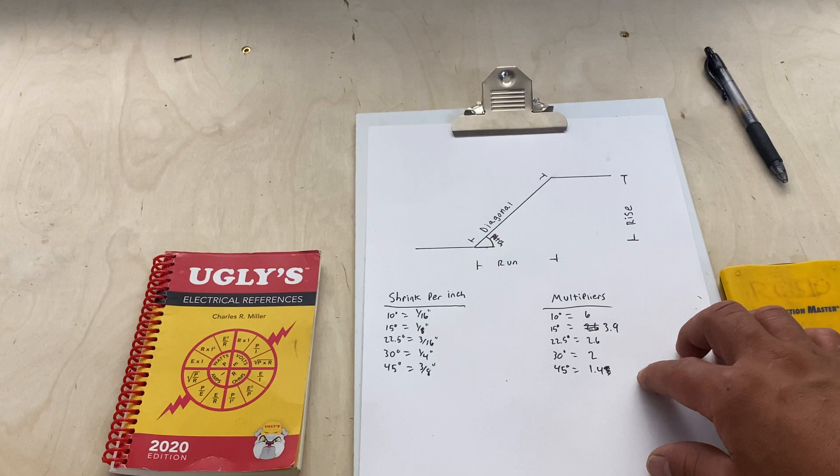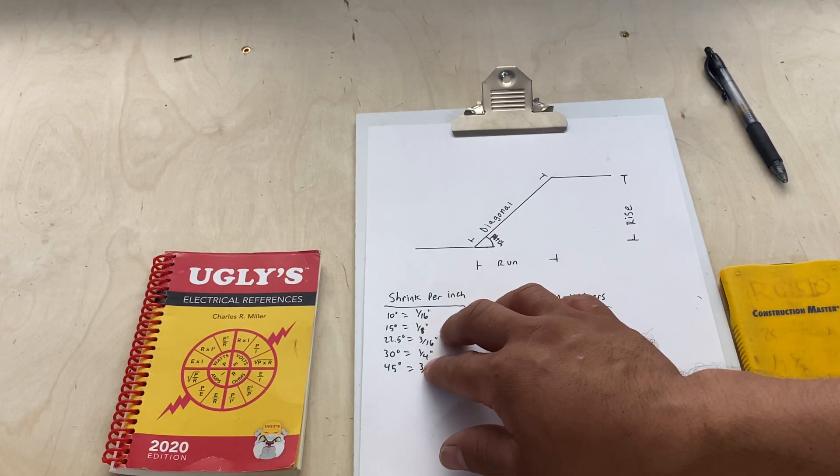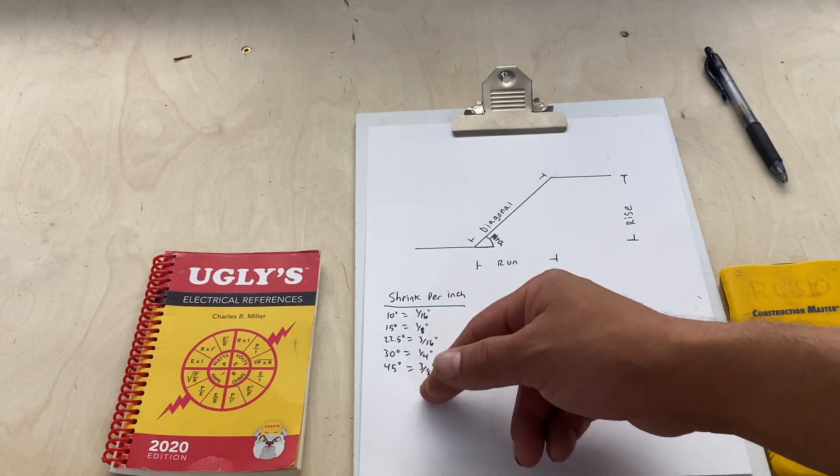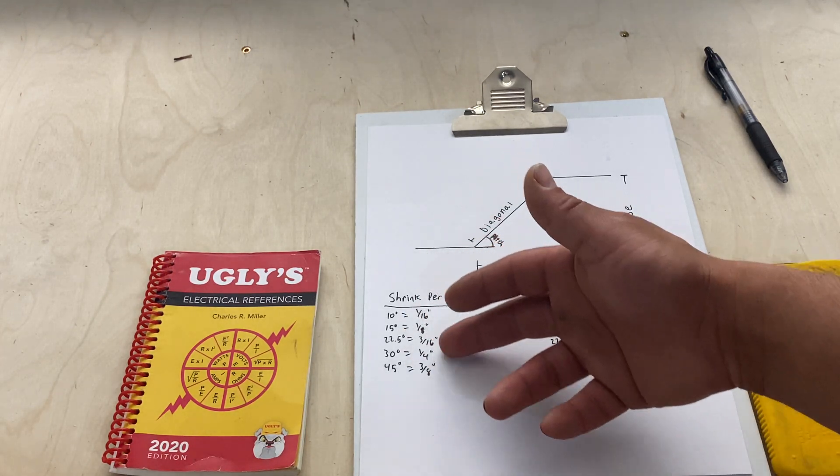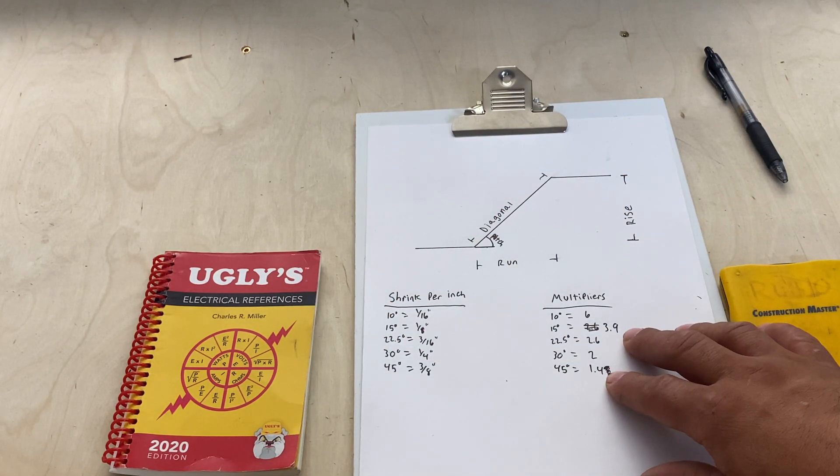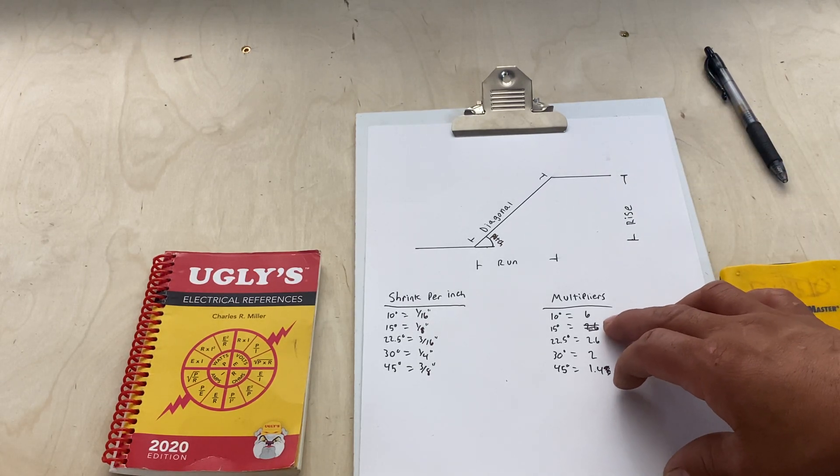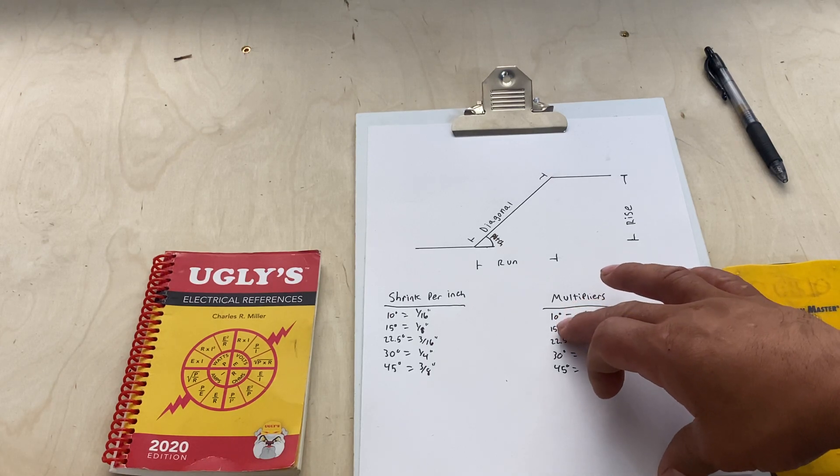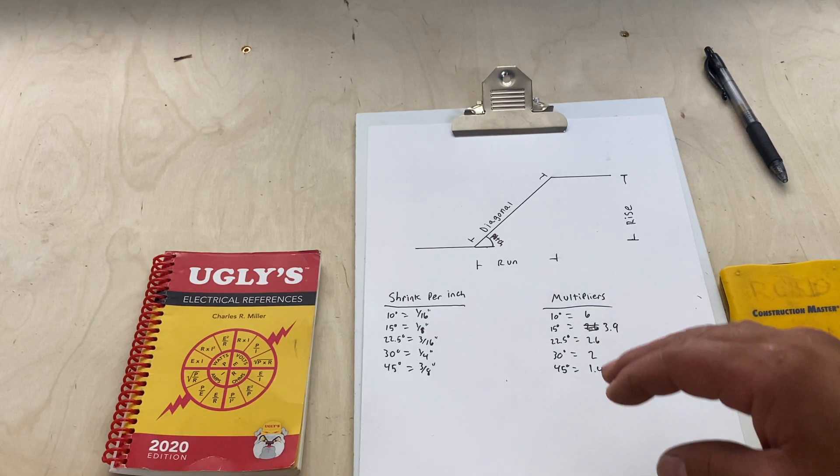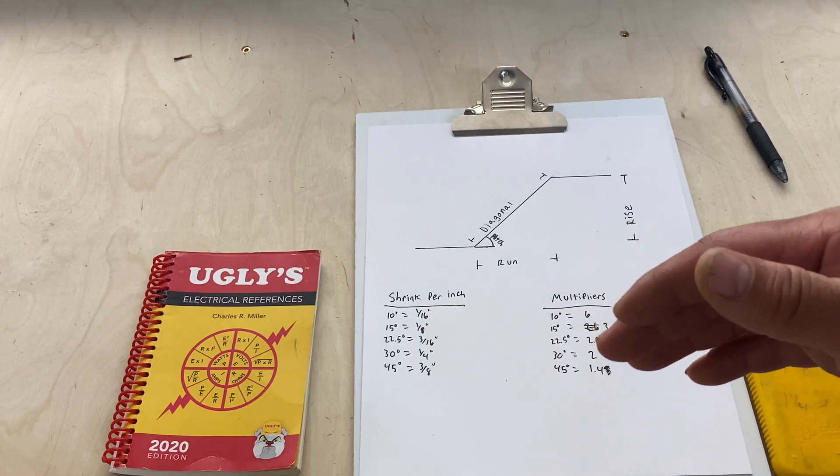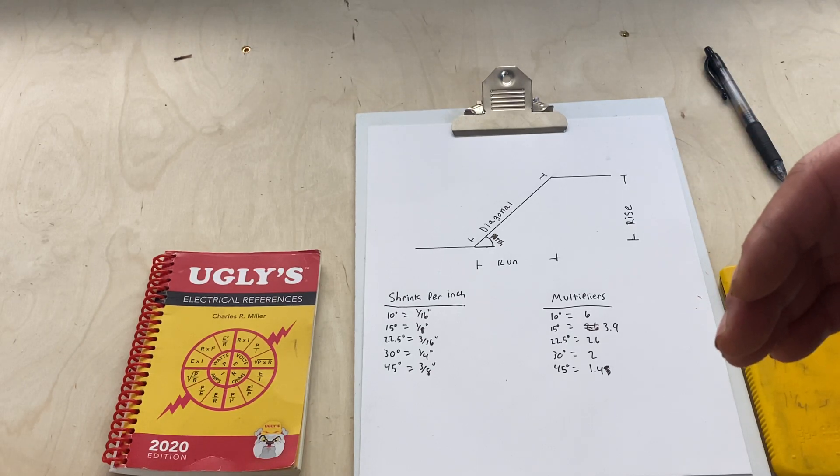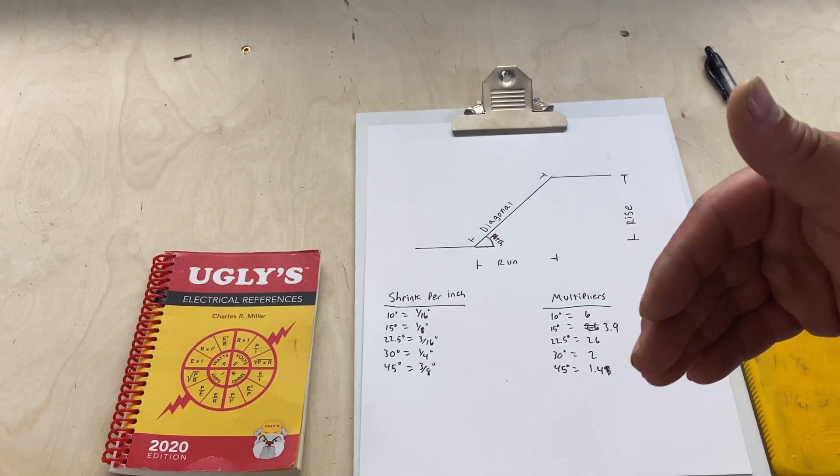The thing about that is this gets you by with solid numbers. If you're doing a three and three-eighths, that's where it starts to get confusing. These are your multipliers, so depending on your rise or your offset that you need, you'll multiply that by one of these numbers depending on what degree you're using. That'll depend on the size of conduit you're using, the workspace you have, and if you want the least amount of pull resistance.